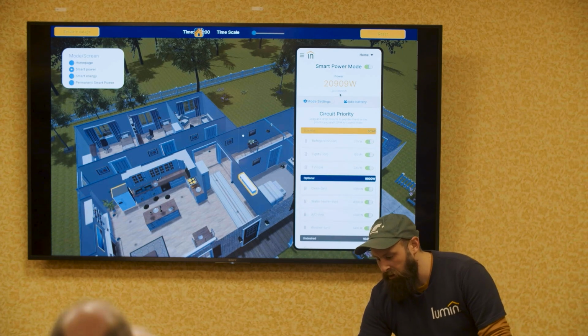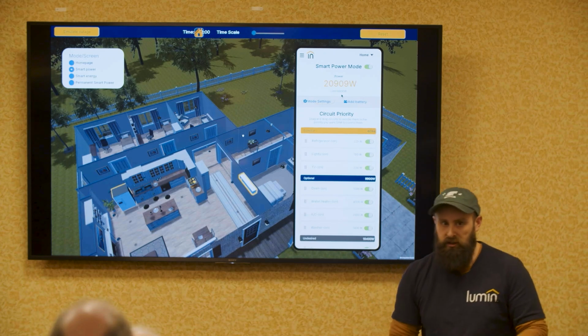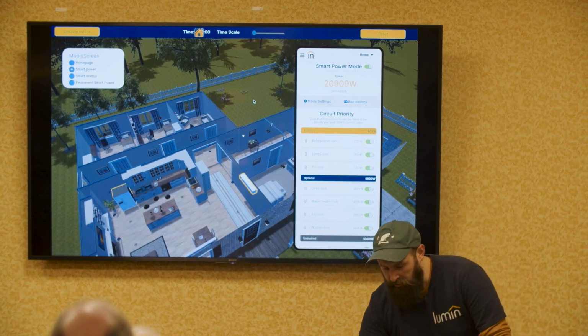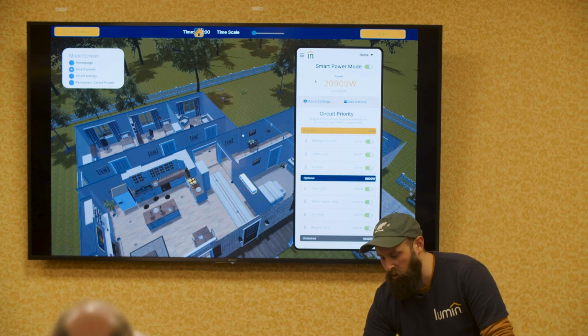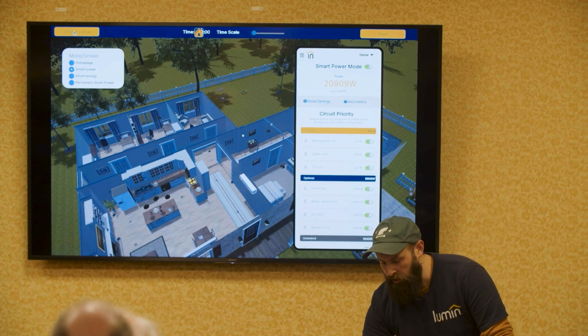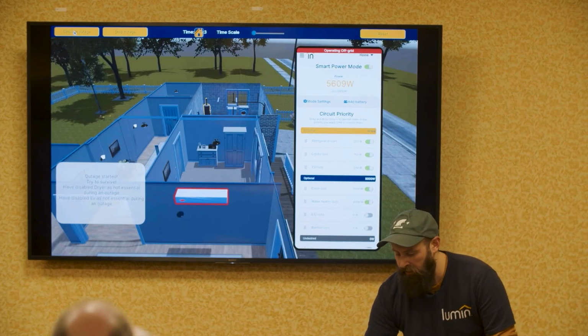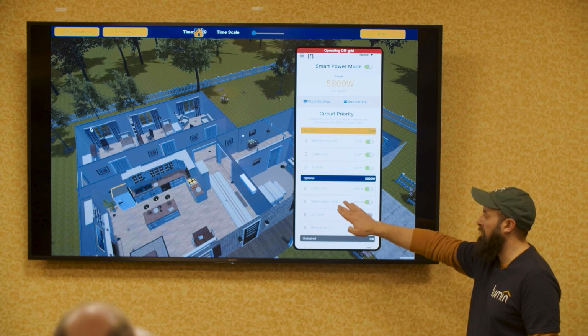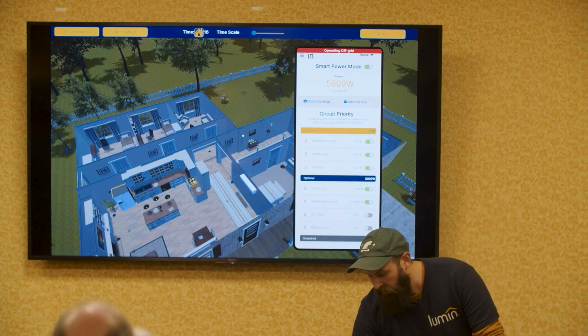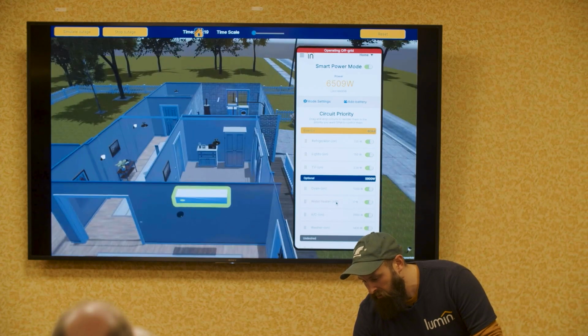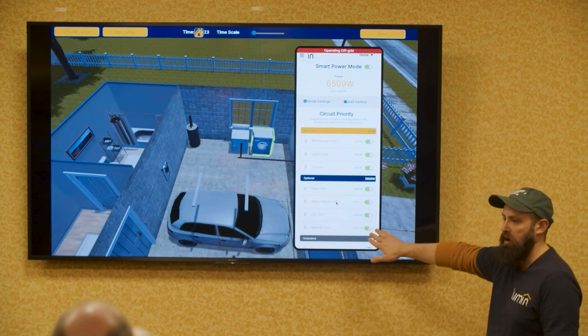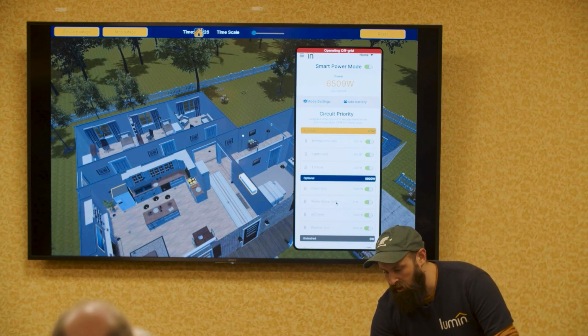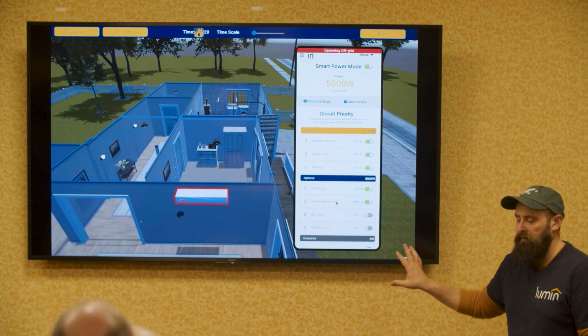We've input a limit of 6,800 watts here, which is what our inverter is capable of outputting. So when an outage happens, we take our roughly 21 kilowatts of usage and shed it down to what the inverter can handle. This elastic total works like this: right now the water heater is ranked in priority above the air conditioner, so the water heater is using 4,000 of our available 6,800 watts. As soon as we're done using the water heater, other circuits with lower priority are allowed to use power. If we start another hot shower, those circuits would then be shed. We're always staying below that output capacity to make sure we don't cause a nuisance trip.